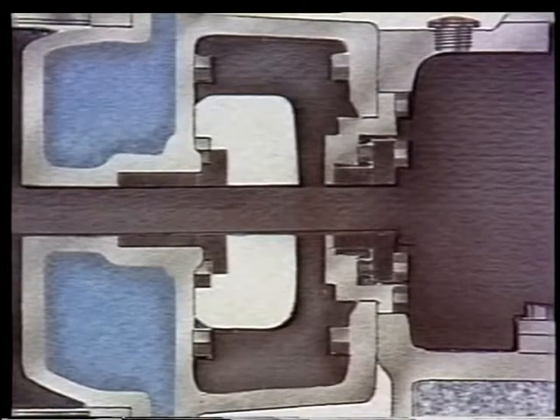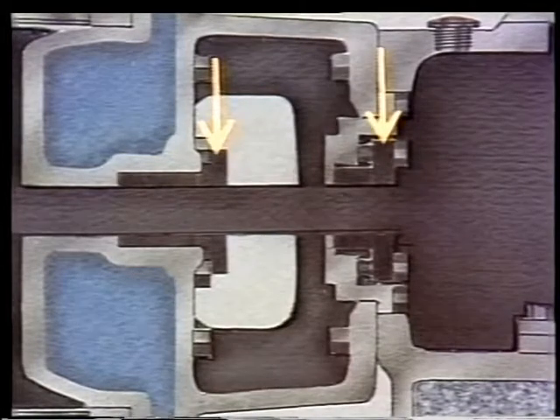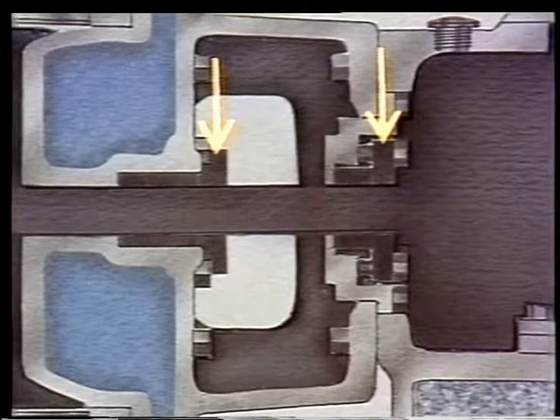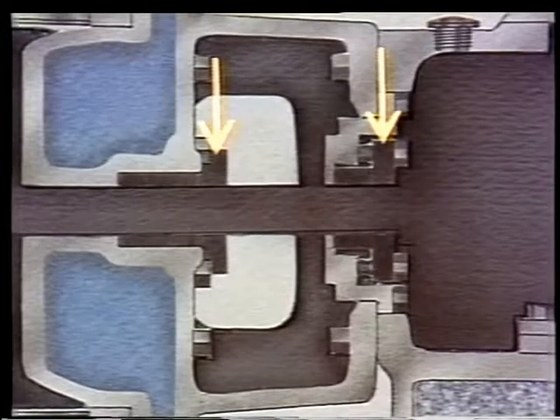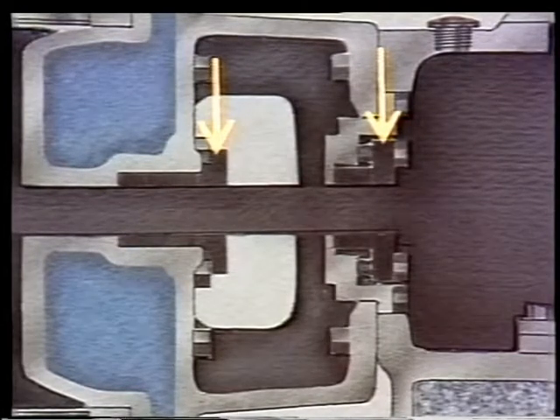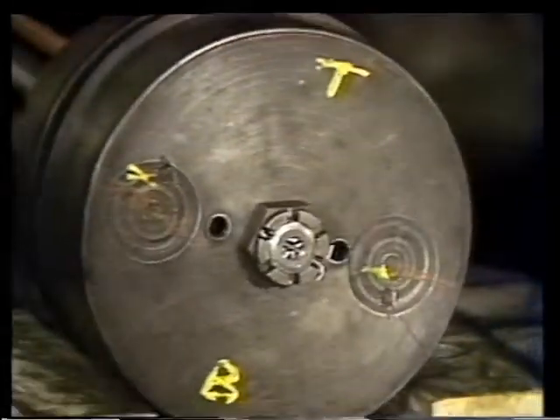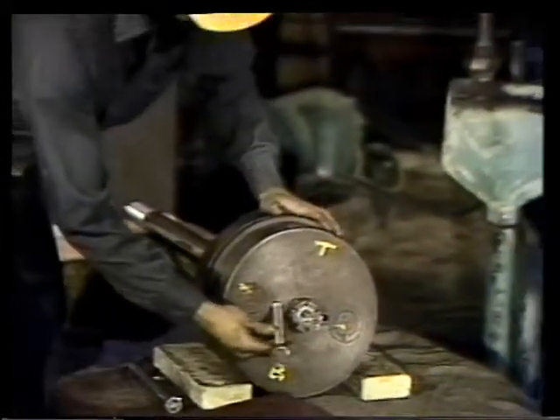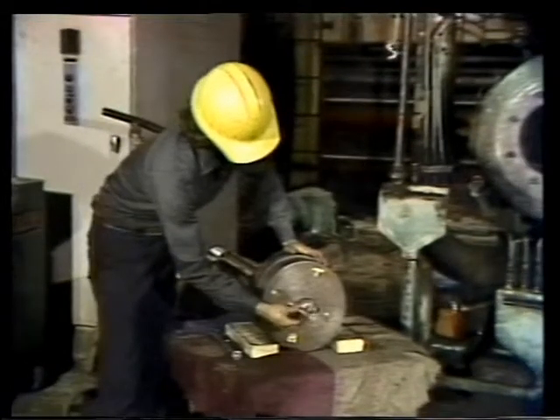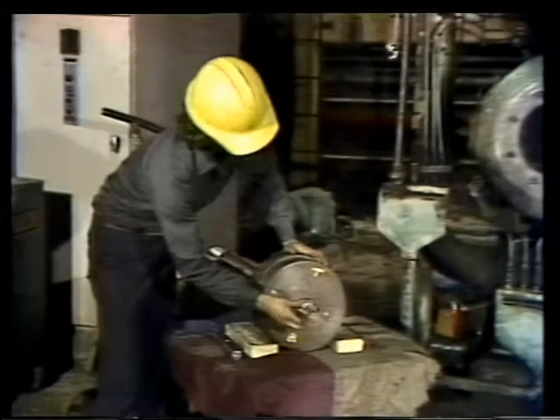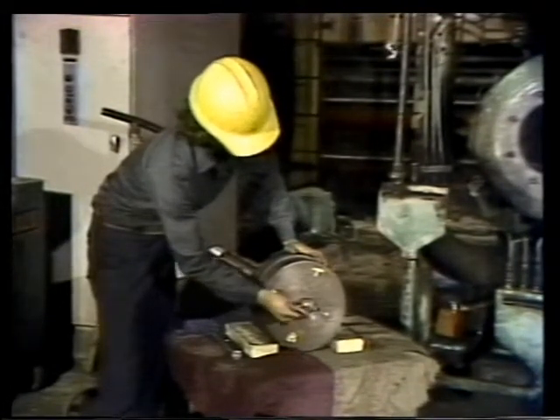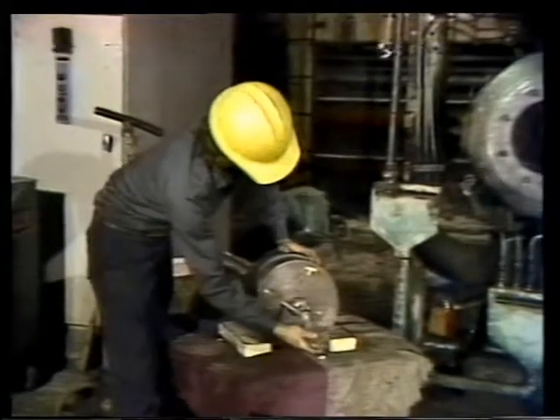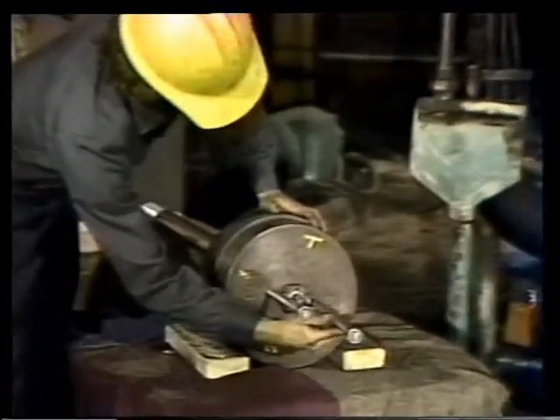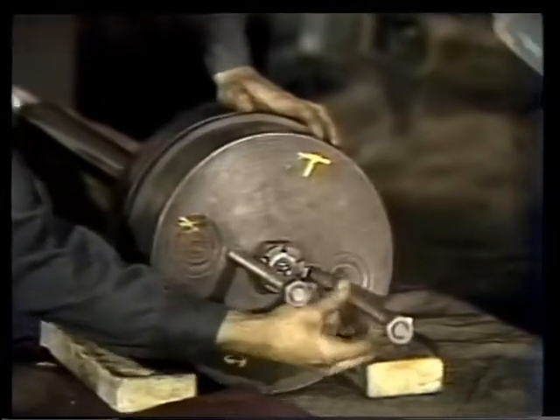But before you do, check that the gland follower and the oil wiper holders are still in place. If they aren't, you'll probably have some difficulty getting the piston assembly into the cylinder. Then screw two long bolts into the piston. These bolts will help you hold the piston when you're putting it into the cylinder. They also give you something to hold onto when you're screwing the piston rod into the crosshead.